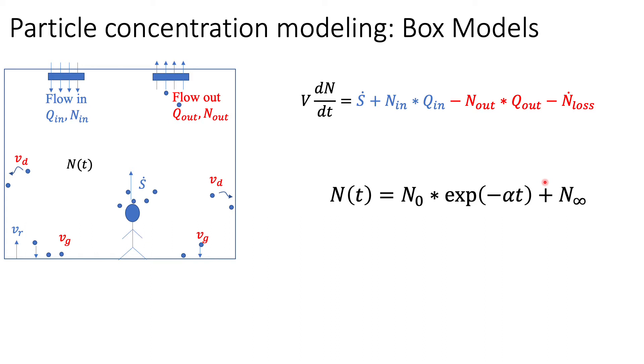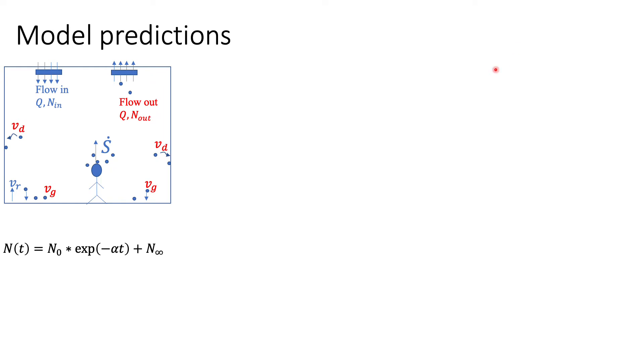To understand the physical meaning of these constants alpha and N infinity, let's look at a simpler case. Consider a person who's talking and breathing, putting out particles in the size range of 500 nanometers to about 5 micron. These particles are not small enough to deposit due to diffusion or big enough to settle down due to gravity. If you are coughing and sneezing, some of these effects become important. In the simple scenario, the important things to consider would be the source rate, the rate at which particles are emitted by this person, and the flow and particles coming in and out with the ventilation system.